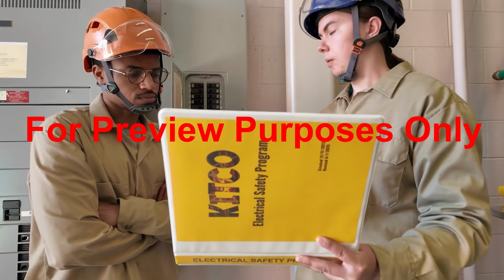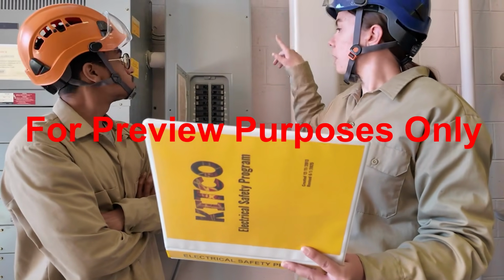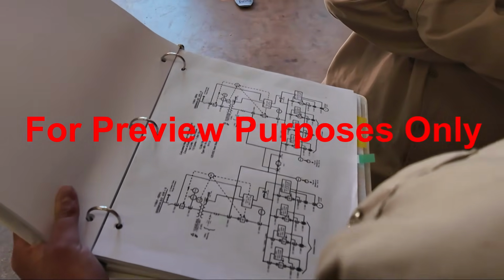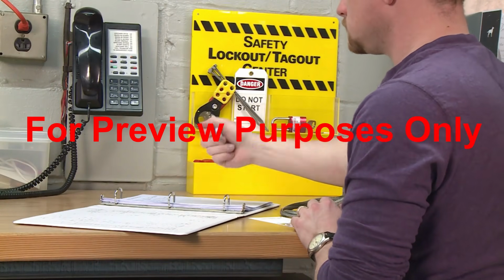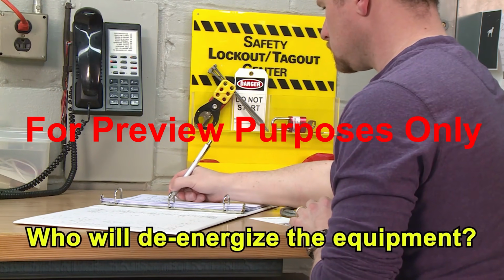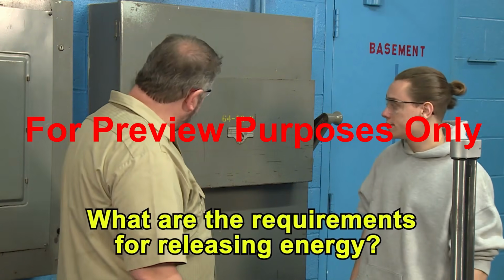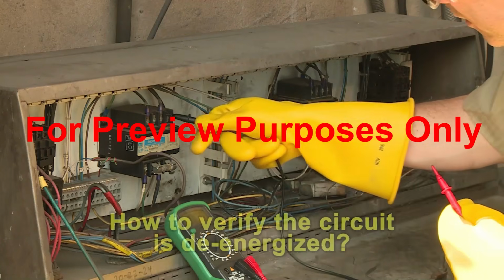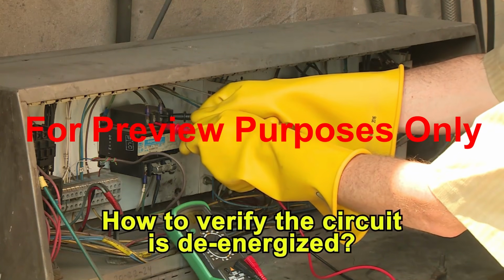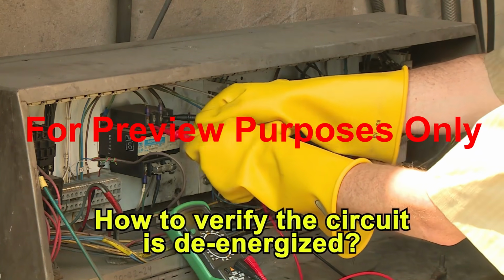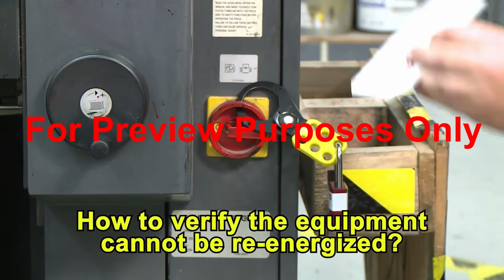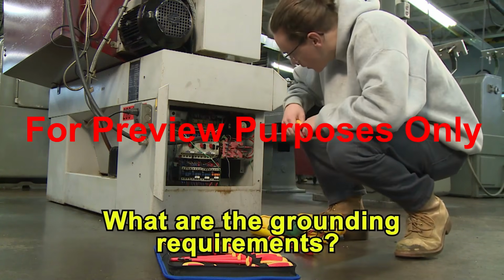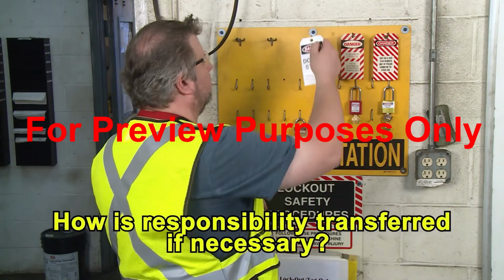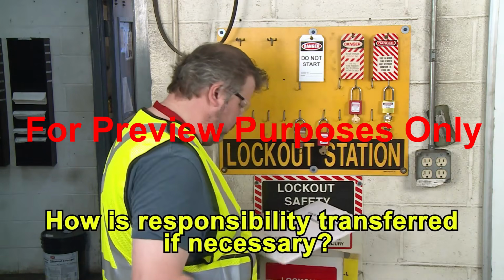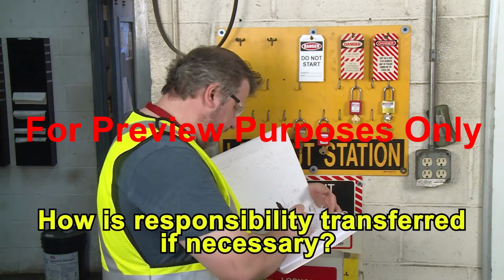Your electrical safety program should include up-to-date drawings and single-line diagrams so that you can determine where the devices should be installed. The lockout-tagout procedures should also identify the person who will de-energize the equipment, the requirements for releasing stored electric or mechanical energy, how to verify that circuits are de-energized as well as the test instruments that should be used, how to verify that the equipment cannot be re-energized, any grounding requirements, and how to transfer responsibility for lockout and tagout procedures to another person if a task takes longer than one shift.